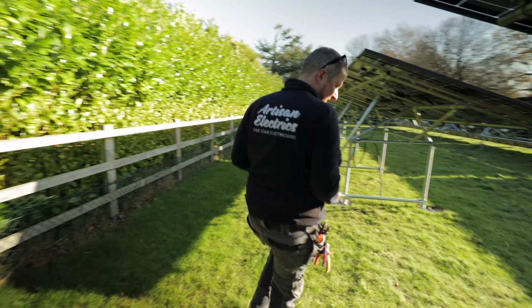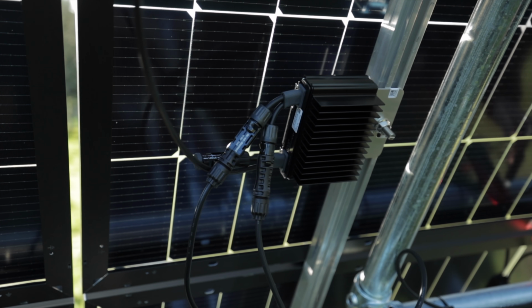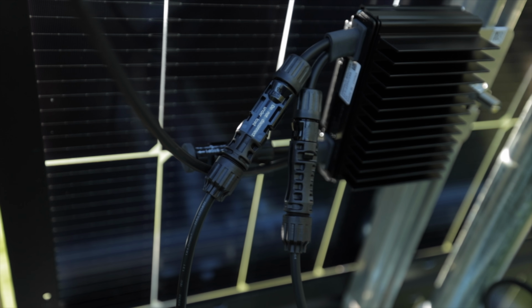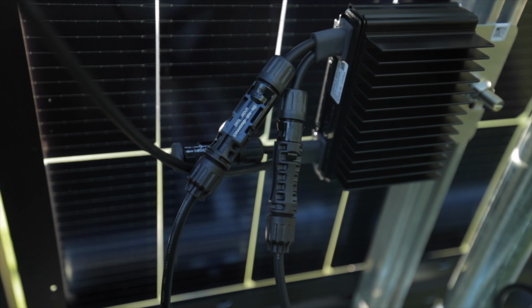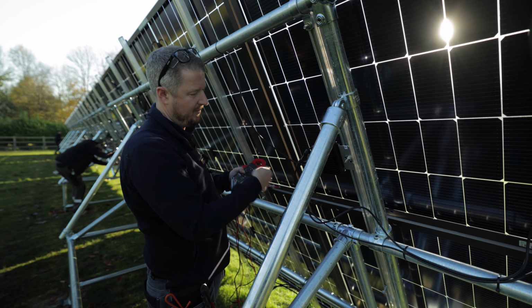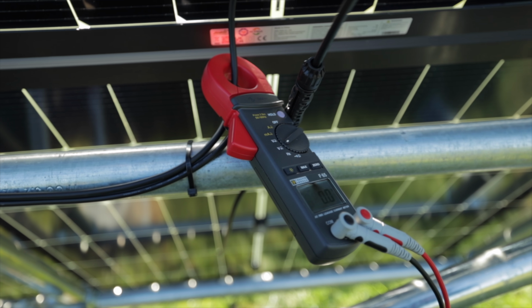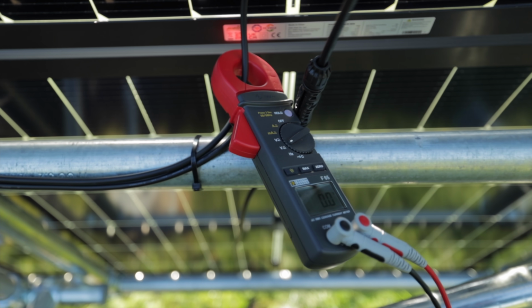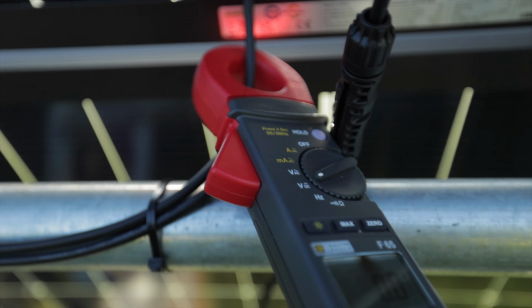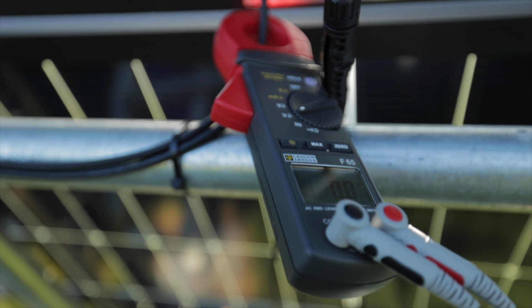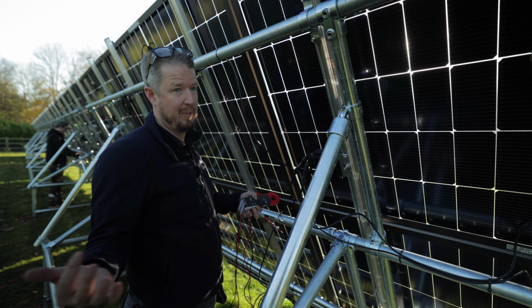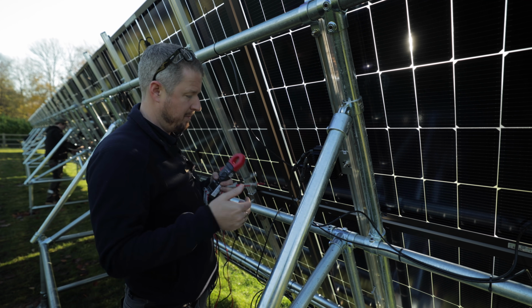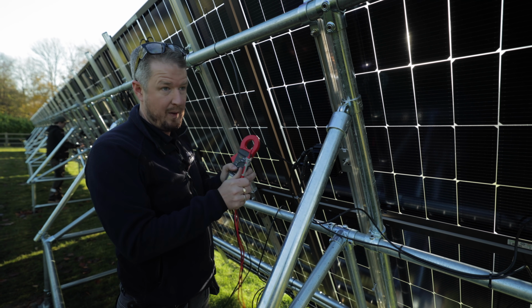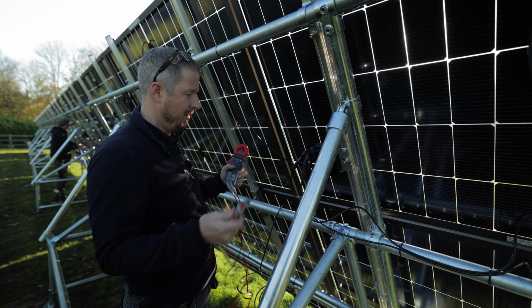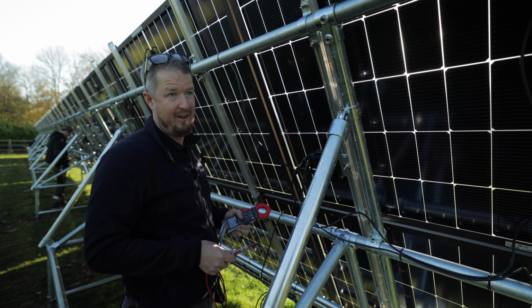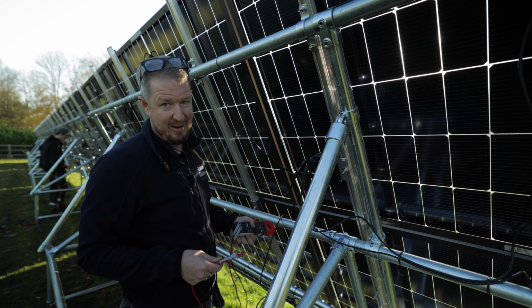Shall we see if we can find this one over here as well then? Essentially, because you've got two short inputs for the panel and then a short and a long one for the optimizer, it's easy to get confused and plug the panel into the wrong side. When that happens, you won't get the exact voltage per optimizer, and you'll find it fluctuating quite a lot. Obviously if you fix it now, it's great, but if you try to liven it up, it could blow an optimizer or create issues. So it's better to test with this voltage meter without putting any power into the system, rather than just plugging the inverter in and finding it doesn't like it and won't let you commission.